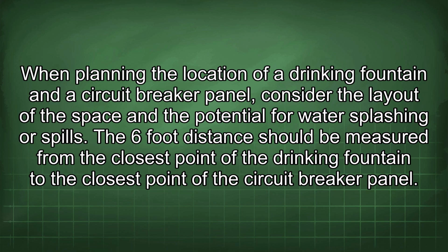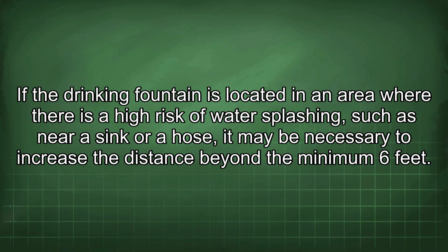The 6-foot distance should be measured from the closest point of the drinking fountain to the closest point of the circuit breaker panel. If the drinking fountain is located in an area where there is a high risk of water splashing, such as near a sink or a hose, it may be necessary to increase the distance beyond the minimum 6 feet.